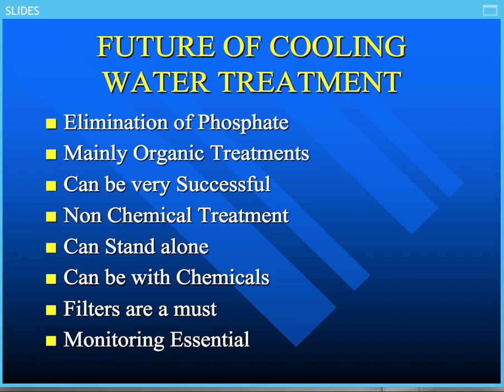But again, as I say, filters are critical and should be a must in every cooling tower system in the country, even the big ones as well as the little ones. And I realize they cost money, but they actually have good return. And back again, what we're talking about is that monitoring is essential. We have to have good monitoring in all of our treatment programs to develop a first-rate cooling water treatment program, to find out, is it working? If it's not working, modify it, change it. But keep on top of it.